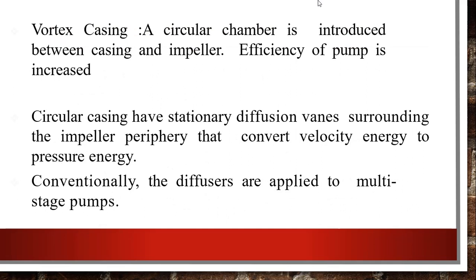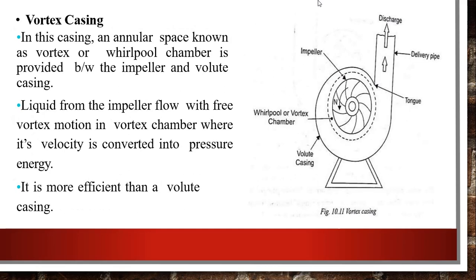In vortex casing, a circular chamber is introduced between the casing and the impeller, which increases the efficiency of the pump. The circular casing has stationary diffusion vanes surrounding the impeller periphery that convert velocity energy into pressure energy. Conventionally, diffusers are applied to multistage pumps. As you can see in this picture, the vortex casing is placed between the impeller and the volute casing.